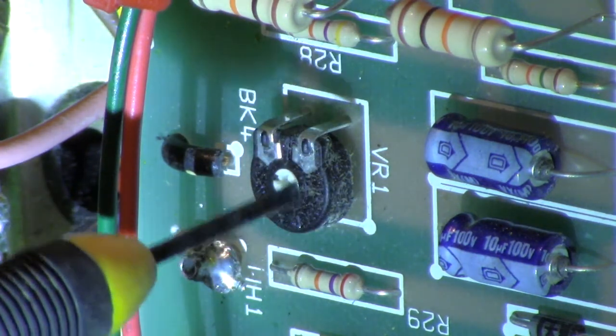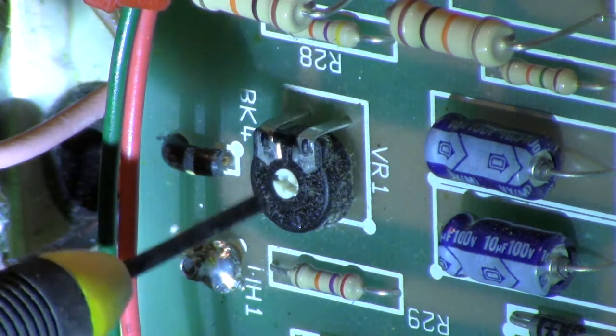We'll see what it reads now and then bring it down to the 39 we got from our equation. This is the default reading right now, so we're pretty close to that 39. We're just going to make a teeny adjustment counterclockwise on this bias adjustment pot, counterclockwise makes the numbers go down, clockwise makes them go up. So we're going to barely turn this to the left, and you can see it going down. It might fluctuate a little bit, so wait a minute, let it settle, and it looks like we're about good to go right there.